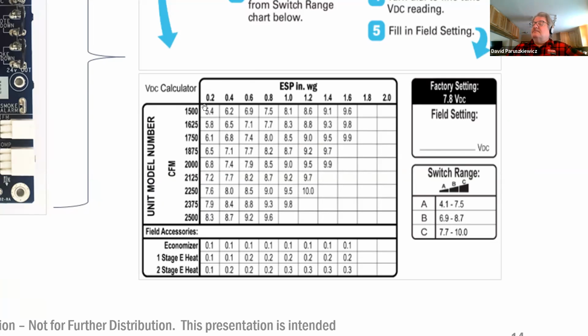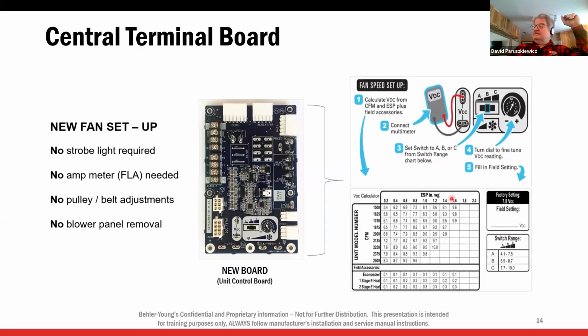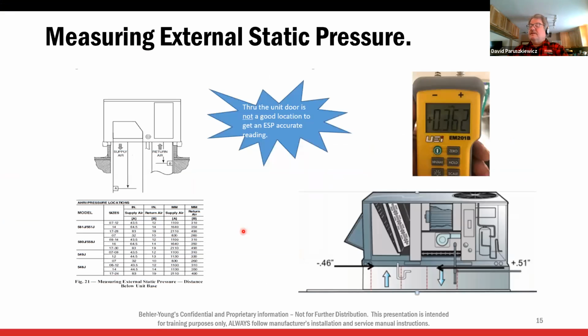So, if I look at this little chart, this is on every one of these units. And across the top, there's my duct static, 0.2, 0.4, 0.6, 0.8, and so on. All right. So we need to adjust the static. This will be done with this little knob right here and this little switch. So the first thing we need to do is measure our static.